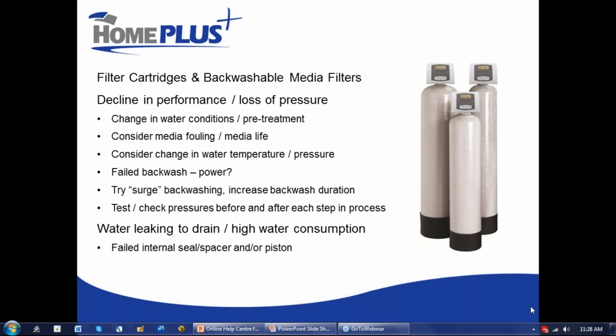Water temperature in the summer is starting to pose some additional problems for us, both in creating more algae blooms, but also in reducing the effectiveness of backwashing of media filters. So this would be true for, again, like Nexsand and Turbidex and other turbidity reduction medias, and also iron filters. As the water temperature increases, the water density drops, and it actually takes more flow rate to achieve the same level of backwash. So we are starting to see some problems on lake water sources in particular, where the water warms up quite a bit in the summer and the effectiveness of backwash decreases. So, something to definitely keep your eyes on.